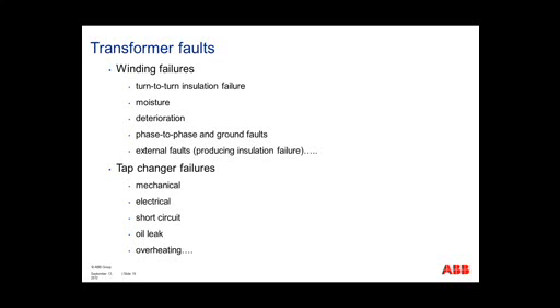So, transformer faults and where the faults occur. For most, we have the winding failures, and this is typically caused by turn-to-turn insulation failures and insulation failures between the windings. Contributing factors could be moisture, deterioration, phase-to-phase ground faults inside the transformer that can break down the insulation in the windings, and external faults. External faults, if not cleared quickly enough, the transformer sees these external faults, even though the fault is not internal to the transformer. These external faults can easily evolve to internal faults if not cleared quickly.